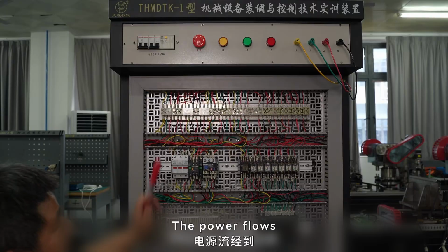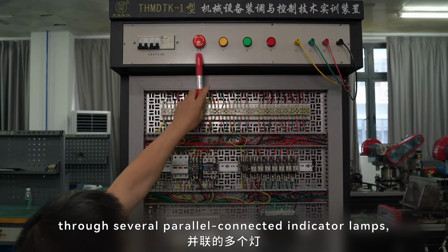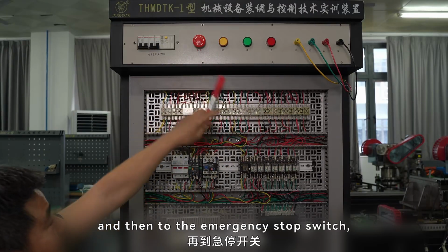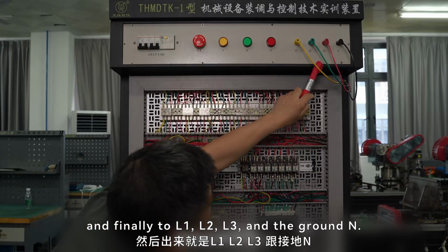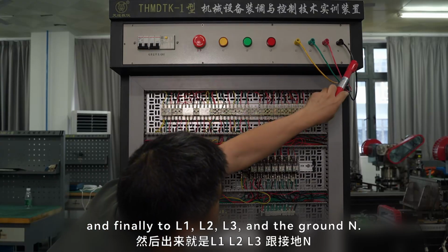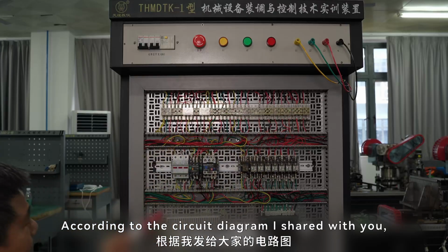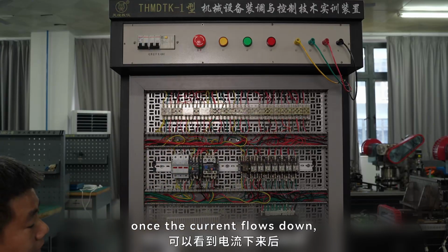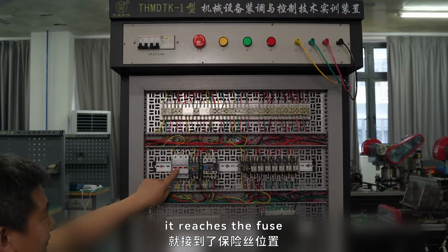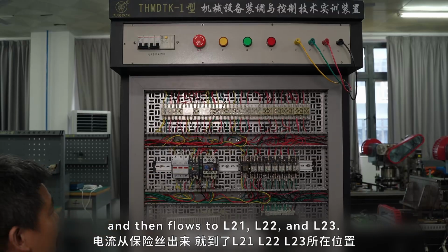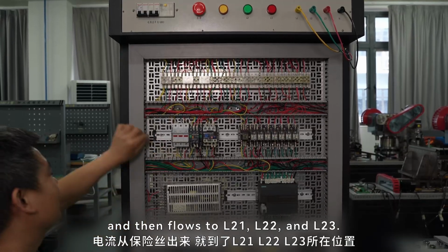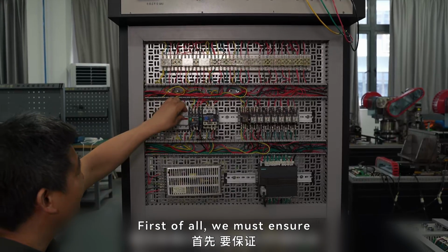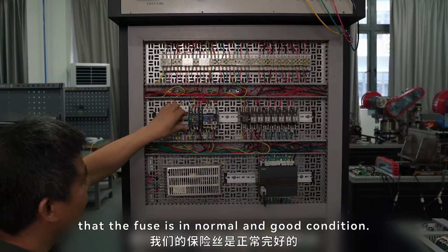The power flows through several parallel connected indicator lamps, and then to the emergency stop switch, and finally to L1, L2, L3, and the ground N. According to the circuit diagram I shared with you, once the current flows down, it reaches the fuse and then flows to L21, L22, and L23. First of all, we must ensure that the fuse is in normal and good condition.